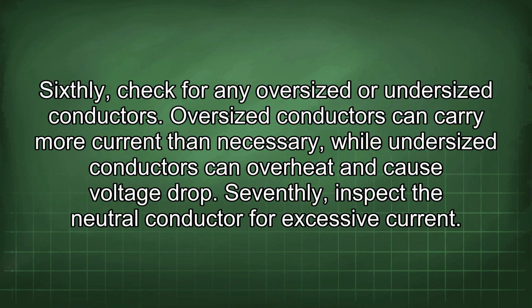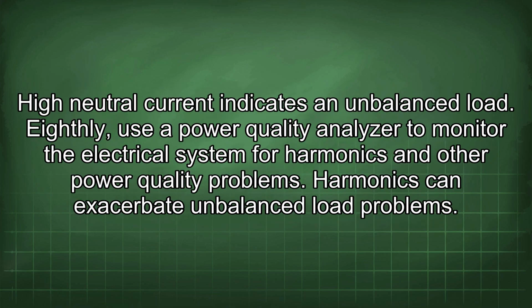Sixthly, check for any oversized or undersized conductors. Oversized conductors can carry more current than necessary, while undersized conductors can overheat and cause voltage drop. Seventhly, inspect the neutral conductor for excessive current. High neutral current indicates an unbalanced load.